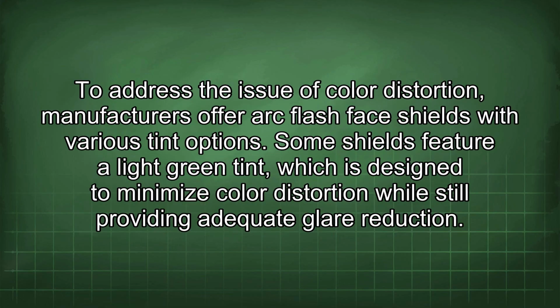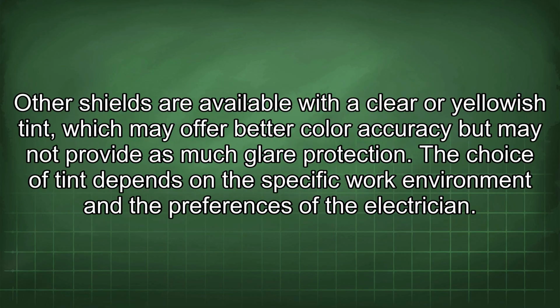To address the issue of color distortion, manufacturers offer arc flash face shields with various tint options. Some shields feature a light green tint, which is designed to minimize color distortion while still providing adequate glare reduction. Other shields are available with a clear or yellowish tint, which may offer better color accuracy but may not provide as much glare protection. The choice of tint depends on the specific work environment and the preferences of the electrician.